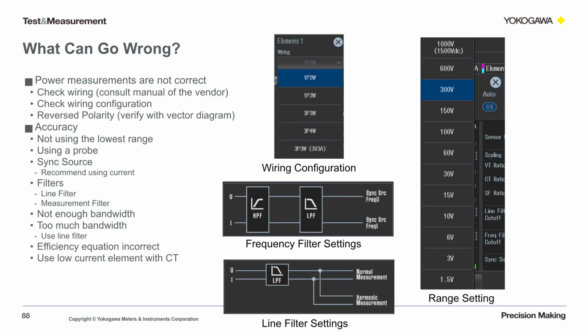If you're already a power analyzer user and not getting the numbers you want, here's a few things to consider. First, check the manual from the vendor to make sure that you're using the right wiring configuration. Also, you might have the reverse polarity. You can quickly verify this using a vector diagram. If your accuracy doesn't seem right, you might not be using the lowest range. As you saw in the accuracy measurements, it depends on the range, and so a higher range setting is going to give you more error.